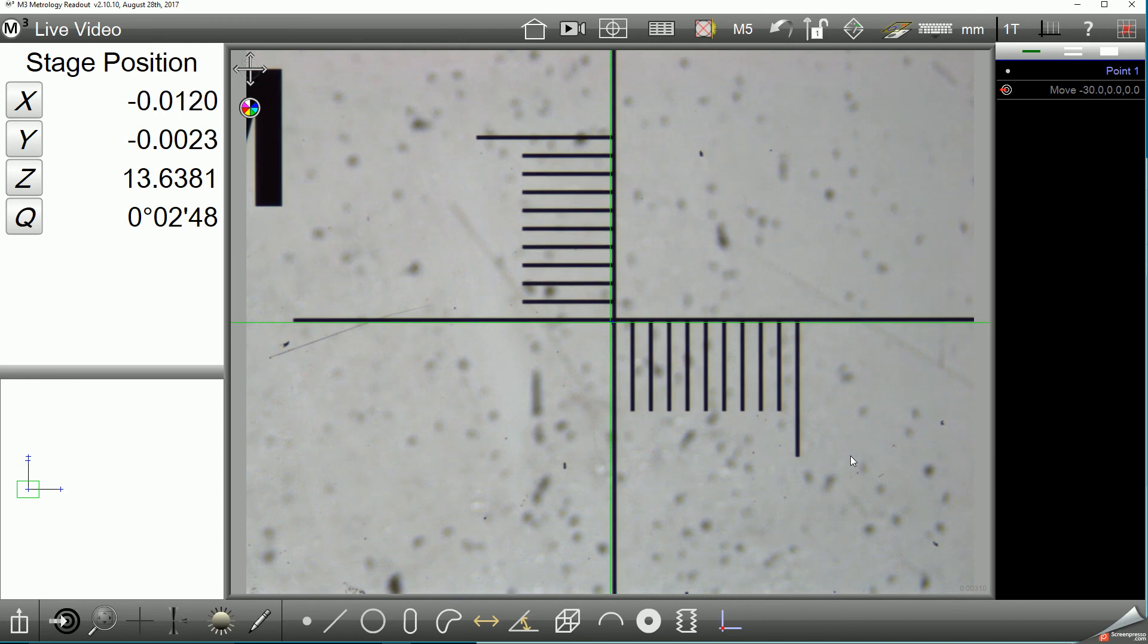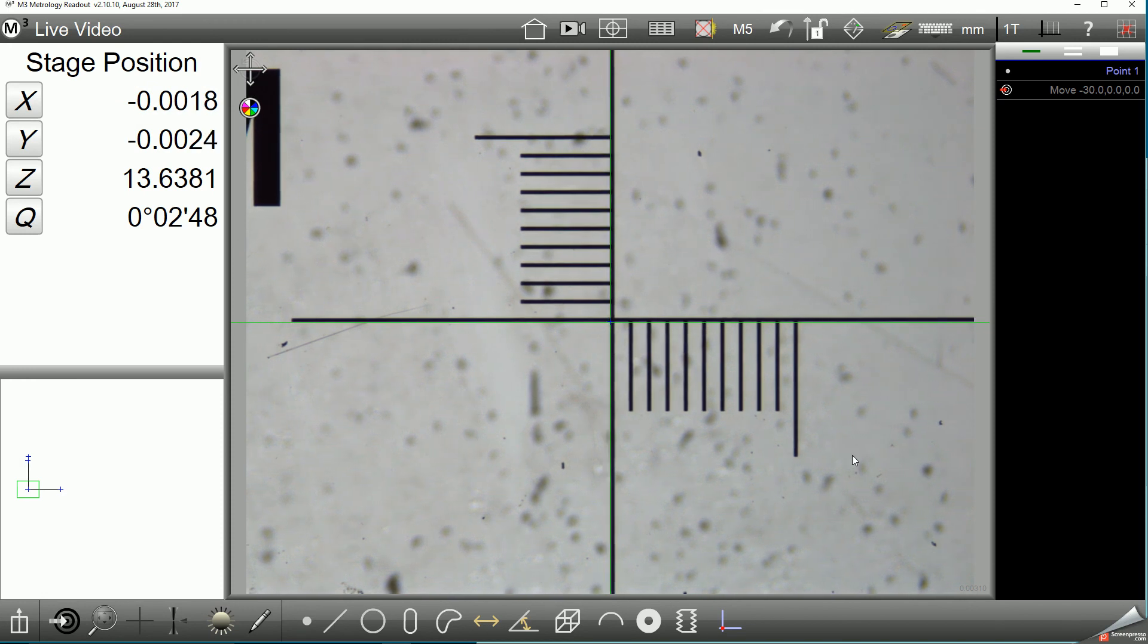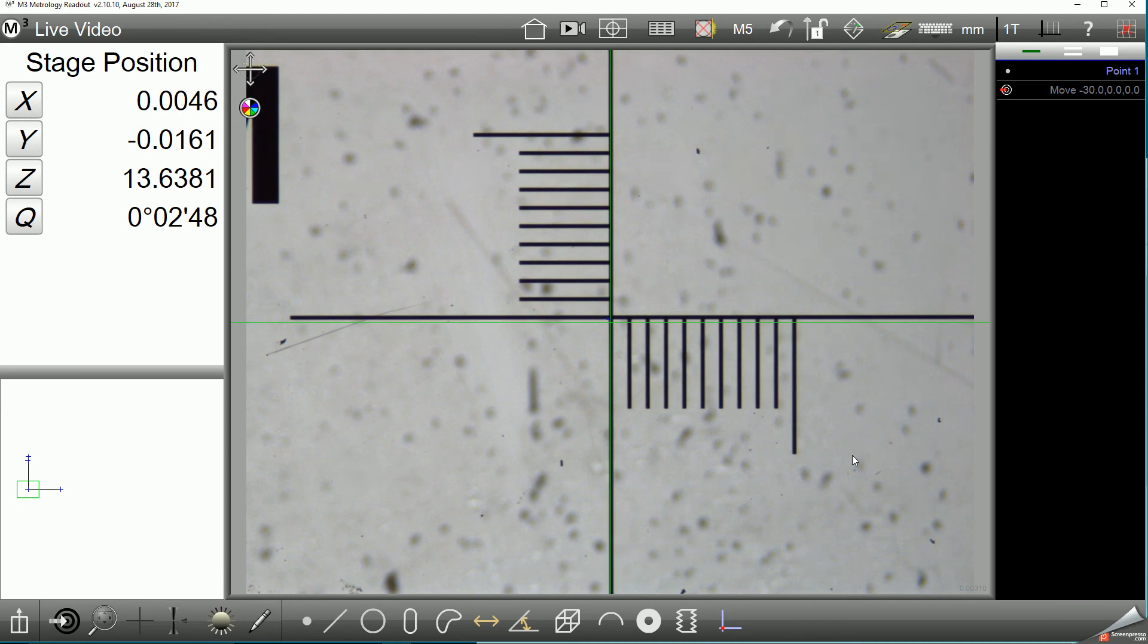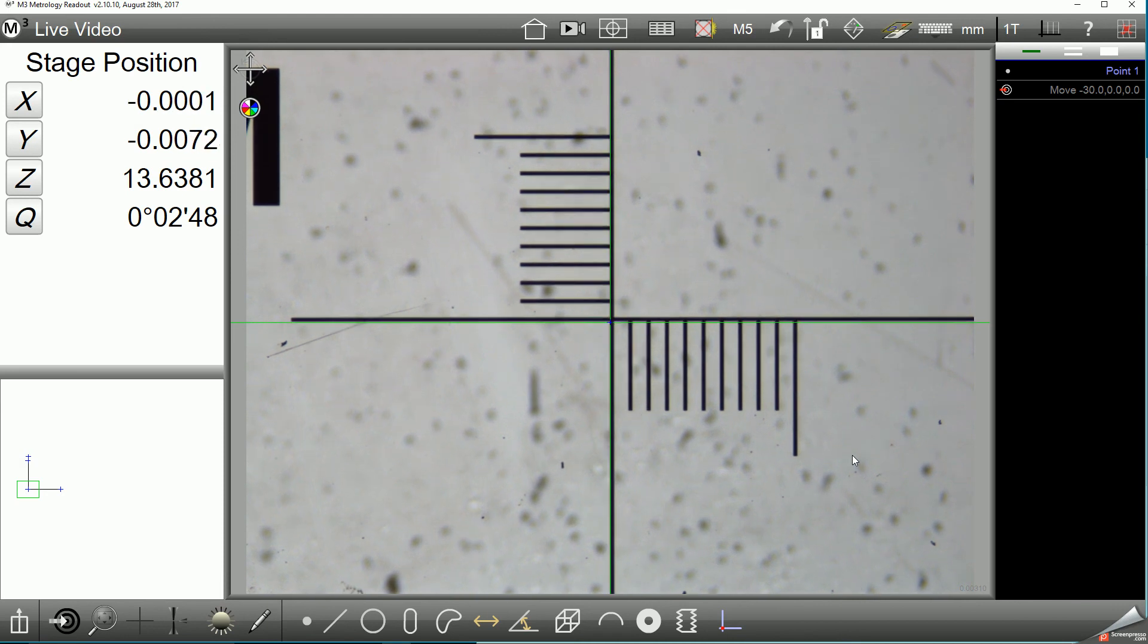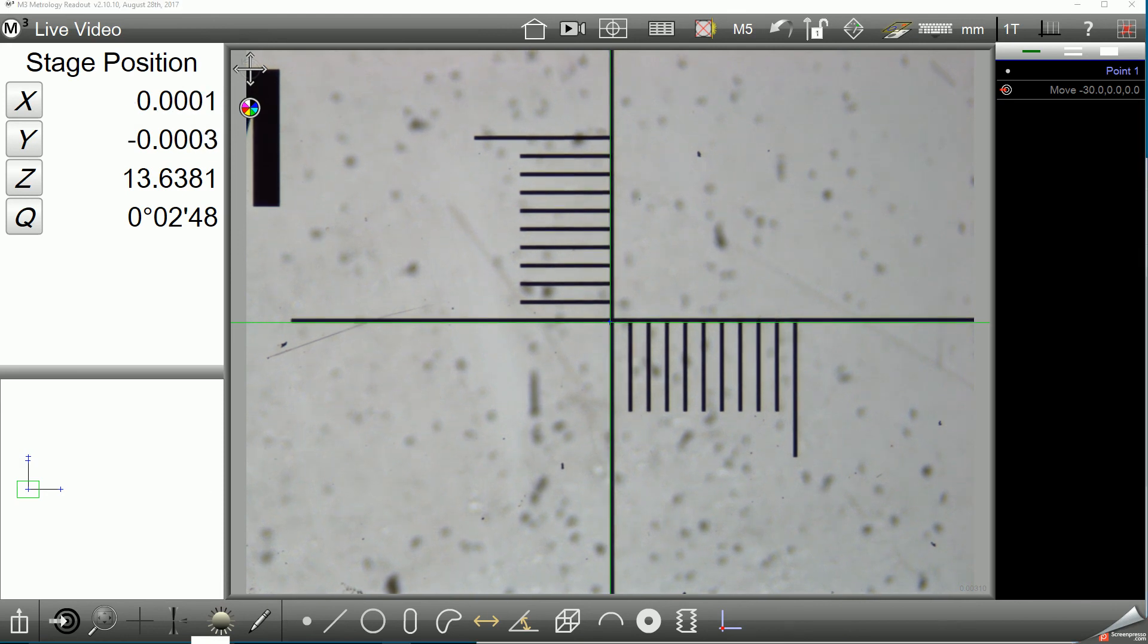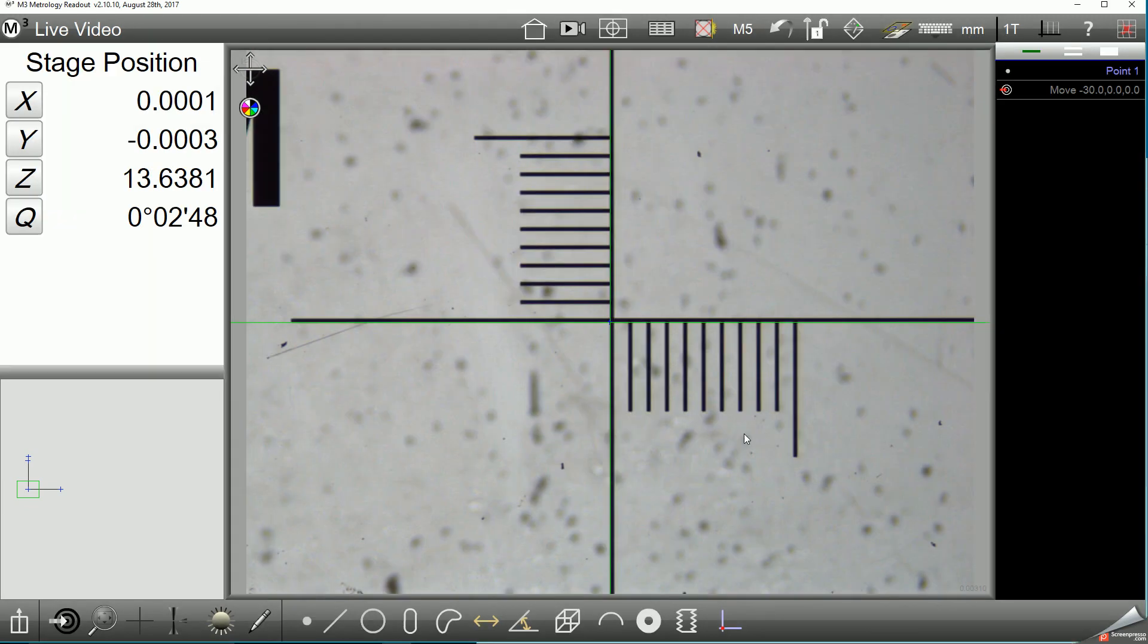I will now proceed to collect the rest of the calibration points on my artifact. For this example, I'm only going to collect three or four segments at five millimeter intervals on my artifact.